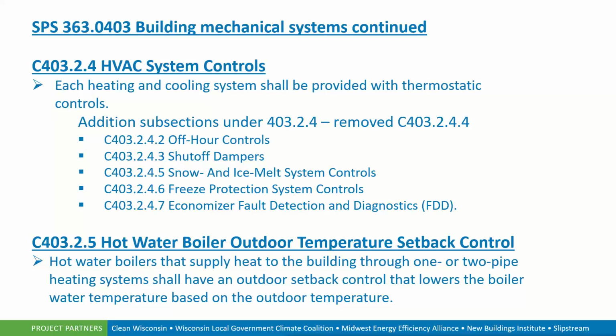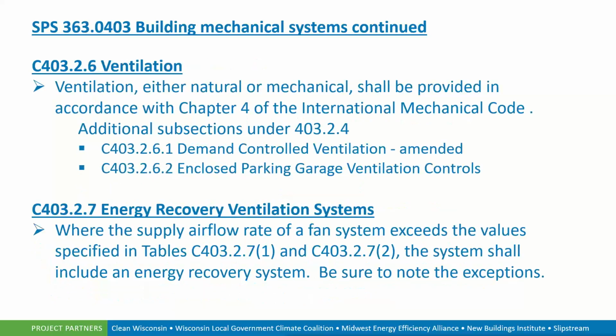We have hot water outdoor boiler temperature setback controls section, making sure that we have those systems in place that lower the boiler temperature based on the outdoor temperature if we have a boiler heating system. We have mechanical ventilation requirements, C403.2.6, and those need to follow Chapter 4 of the International Mechanical Code. We have some additional subsections under 403.2.4: demand control ventilation was amended, and they added enclosed parking garage ventilation controls.